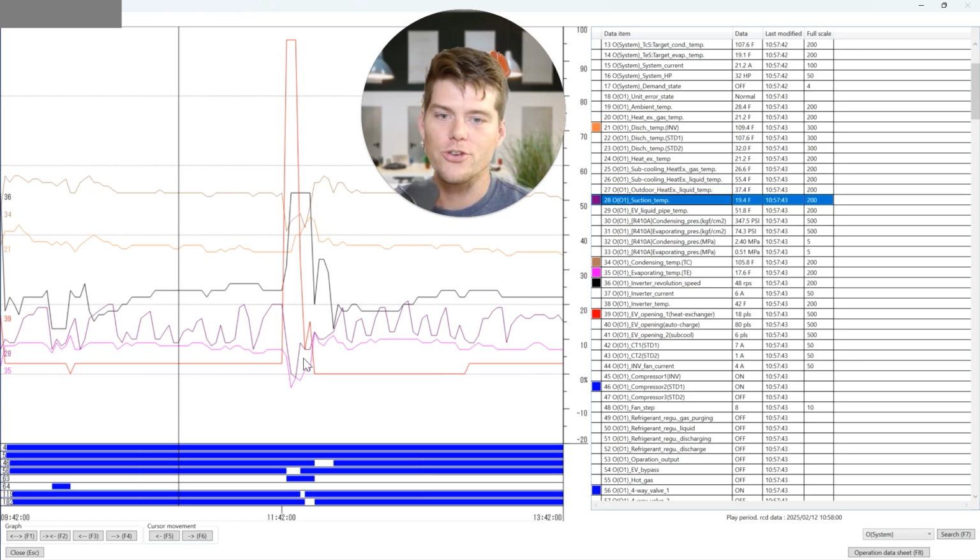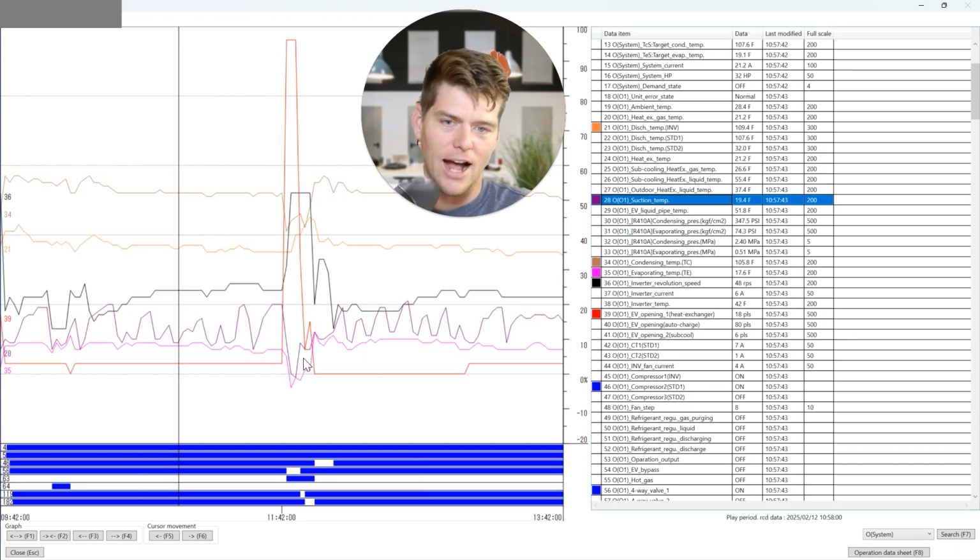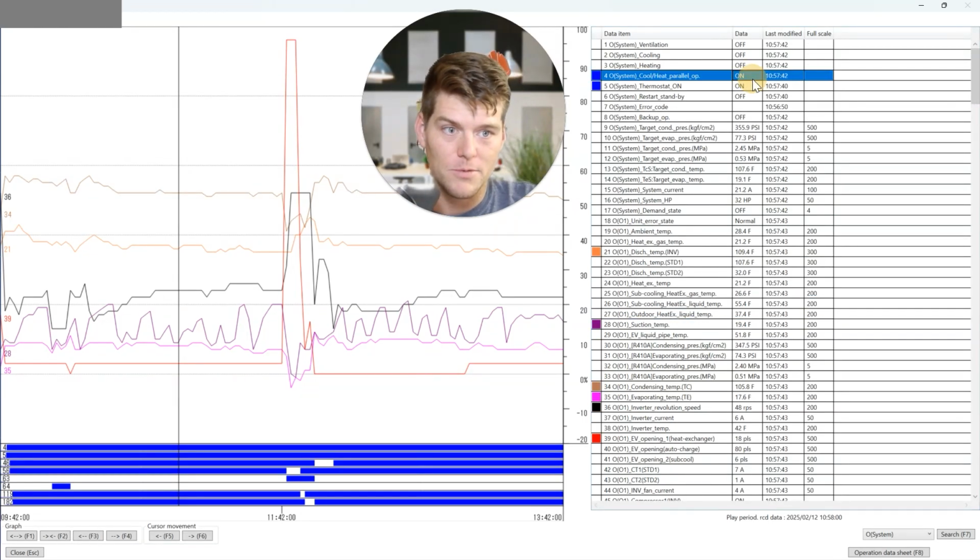Ooh, there's that word, surge. It's going up, and then it's going back down, and then it's going up, and then it's going back down. And again, that's because liquid refrigerant is bypassing somewhere. Now, if this was liquid refrigerant at a constant coming down the suction line, which it wouldn't be because we're in parallel mode, which is a mode we kind of skipped over there.